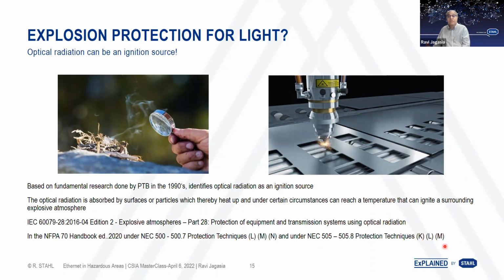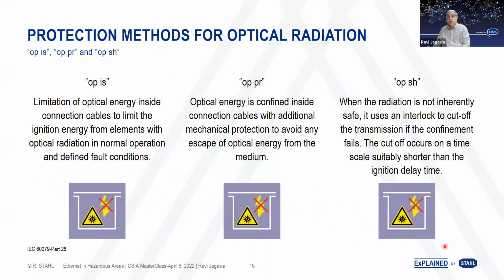So what are these 3 protection methods? These are OP, IS. Don't mix it up with intrinsic safety. It's nearly the same or very close. It is OP, inherently safe. Basically, it limits the optical energy running through the cables, which in turn becomes a very limited ignition energy, and it doesn't create an explosion, whether it is in normal operation or in defined fault operation.